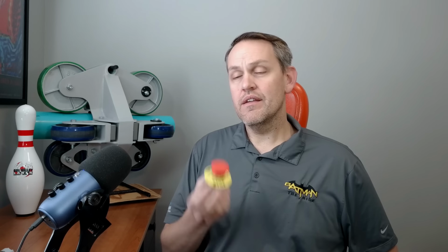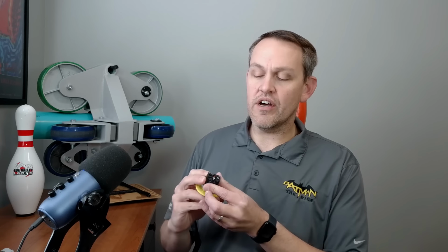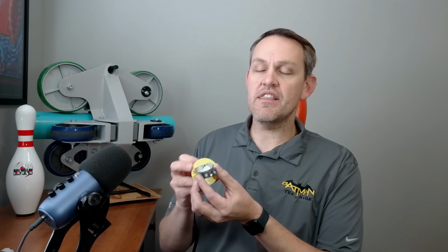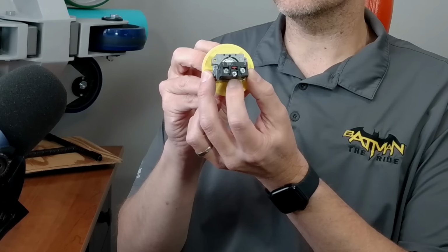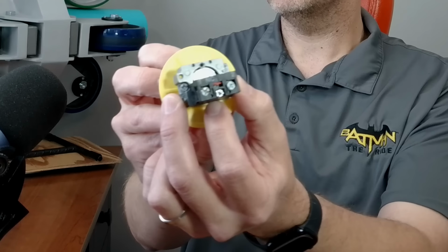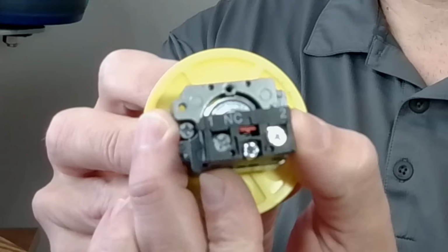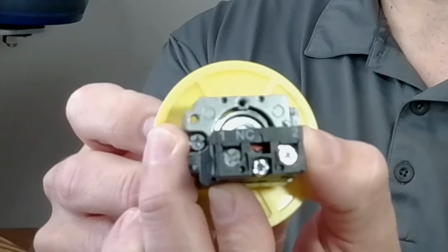The ESR, so the emergency stop powers the ESR circuit. Emergency stop relay is typically what that is. So the emergency stop relay is typically a physical relay in the cabinet. It's a very large relay, which means it has tons of contacts. On the back of here, these guys allow what's called contact stacking. Like if you can see that little red indicator that sits right there. That red indicator, when I open this up, it retracts back in.